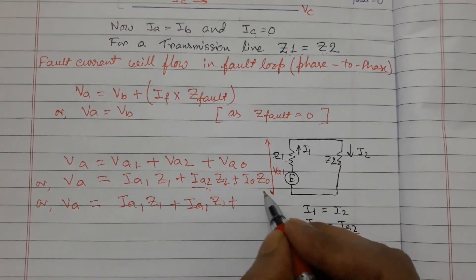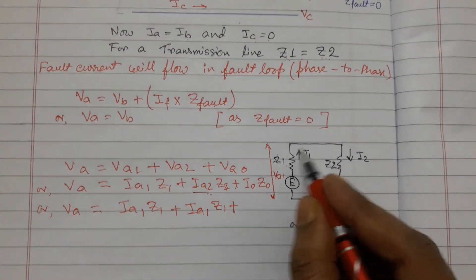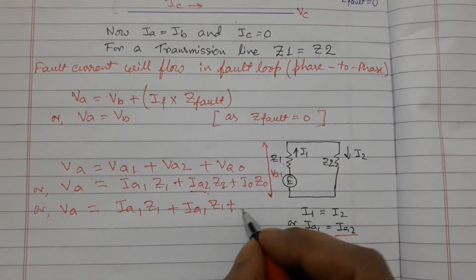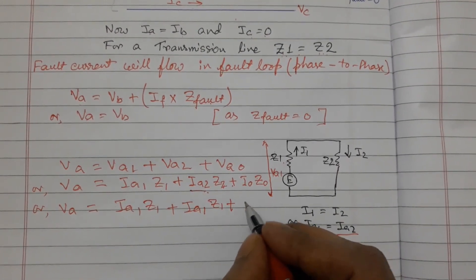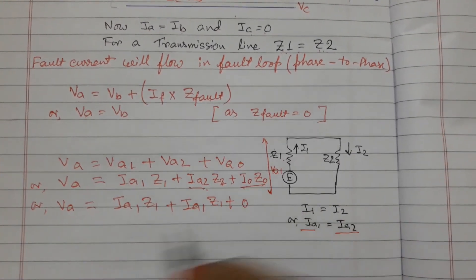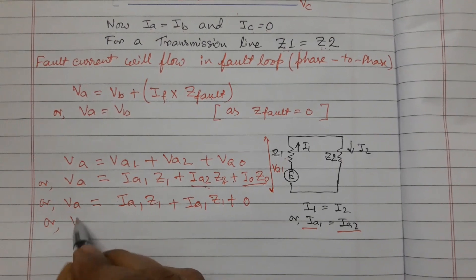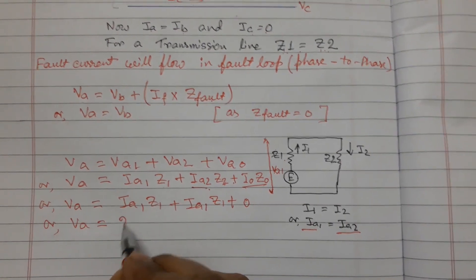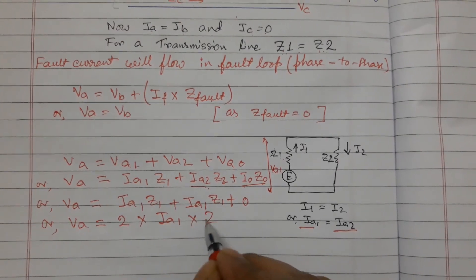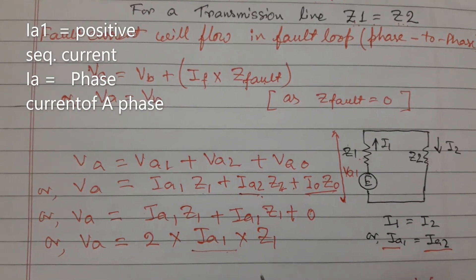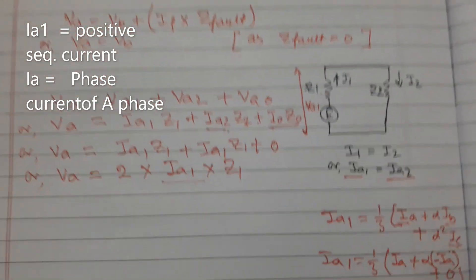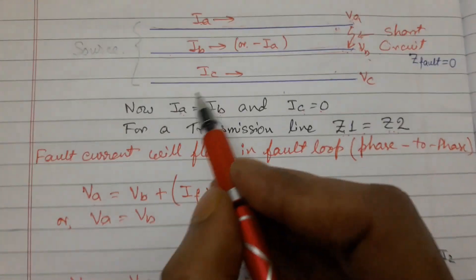In a line-to-line fault, the zero sequence current Ia0 is zero, so that term drops out. Therefore we can write Va equals 2·Ia1·Z1. Now we will substitute the value of Ia1 in terms of Ia, where Ia is the actual fault current flowing in the circuit.